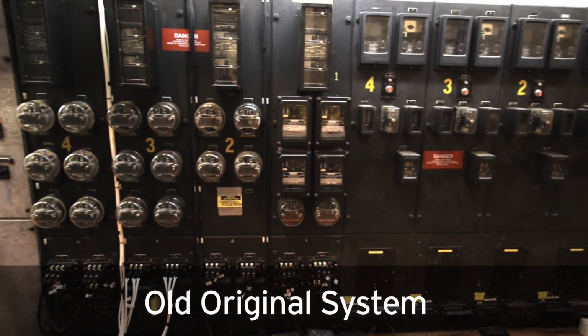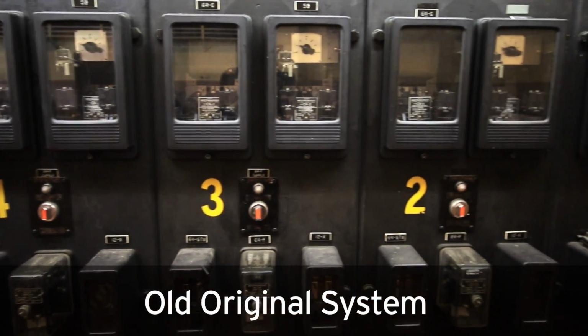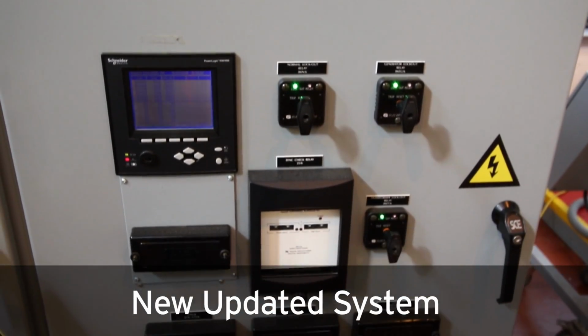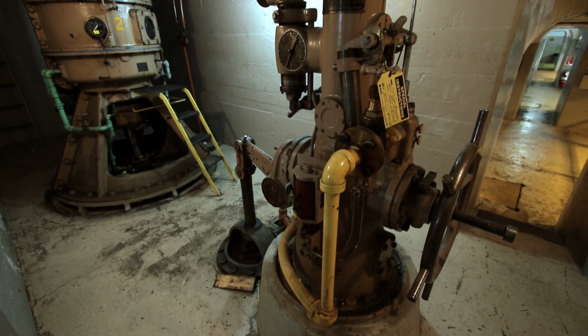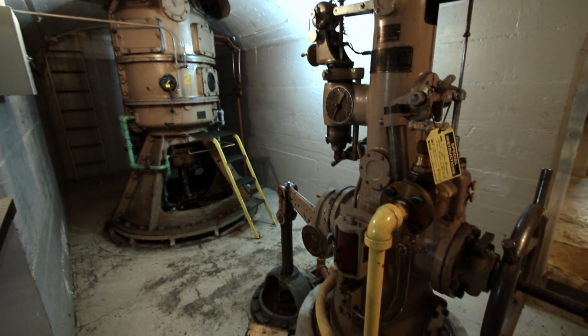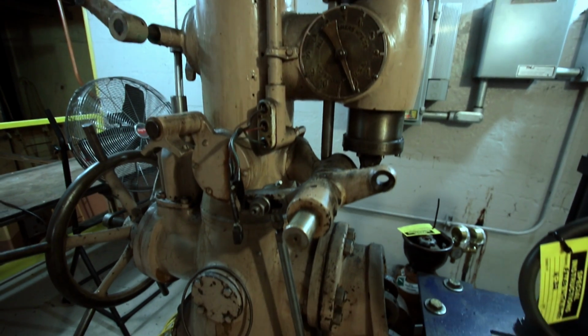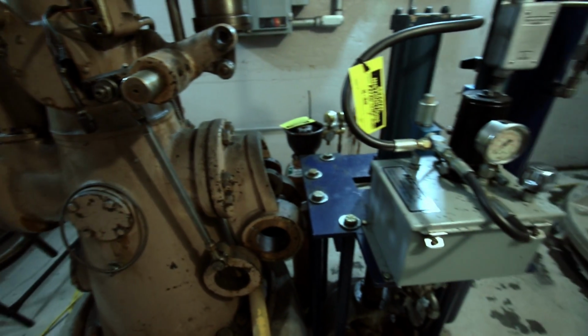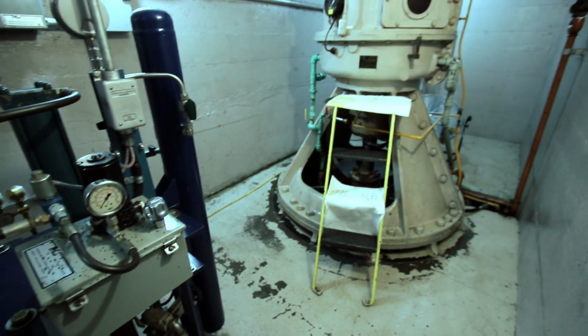For example, the protection and control system is mainly vintage electromechanical relays. Their age gives rise to a number of operational issues, including the unavailability of spare parts and lack of in-house expertise. The exciter and governor systems are original and are very unreliable. Parts are no longer manufactured, so maintenance requires either removing parts from other older equipment or we just have to custom manufacture it. Also, these governors cannot initiate a unit trip, so the only way to stop a unit is to manually close the wicket gates and apply the brakes. If that doesn't work, we have to drop our head gates while the unit's running. This is a very dangerous procedure and really puts our employees at risk.